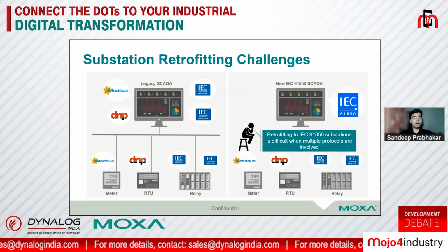The 61850 protocol should be compatible with that, and the power SCADA has to monitor these legacy meters, RTUs, relays, and all those things. Those field devices are running protocols like Modbus, DNP3, IEC 101 and 104, which makes it difficult to integrate the field devices to SCADA.